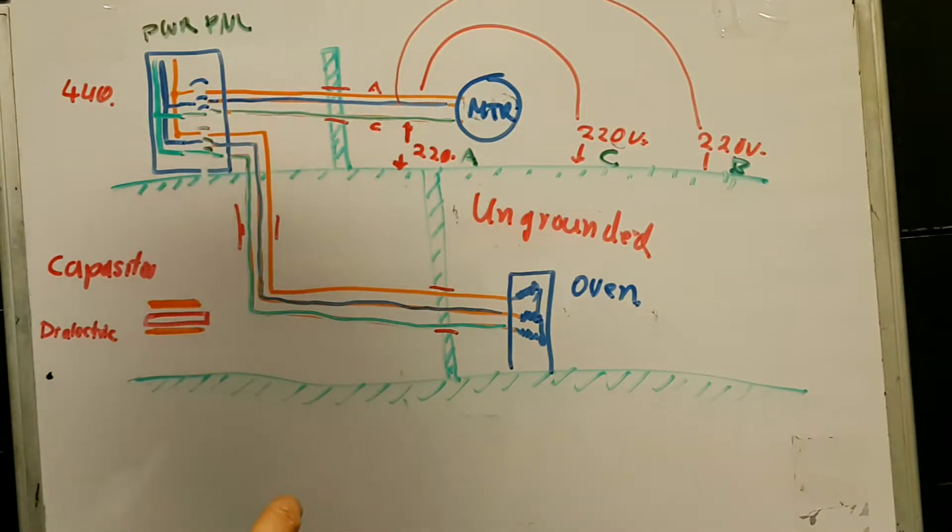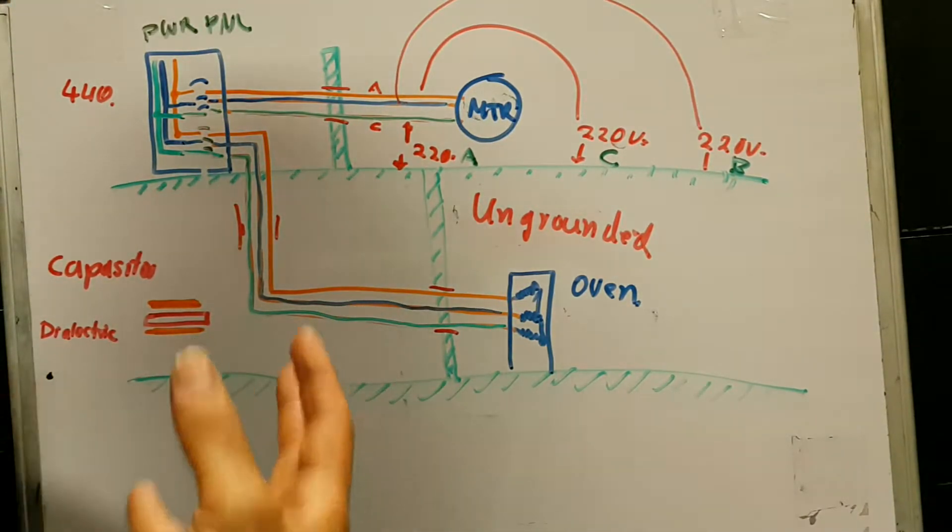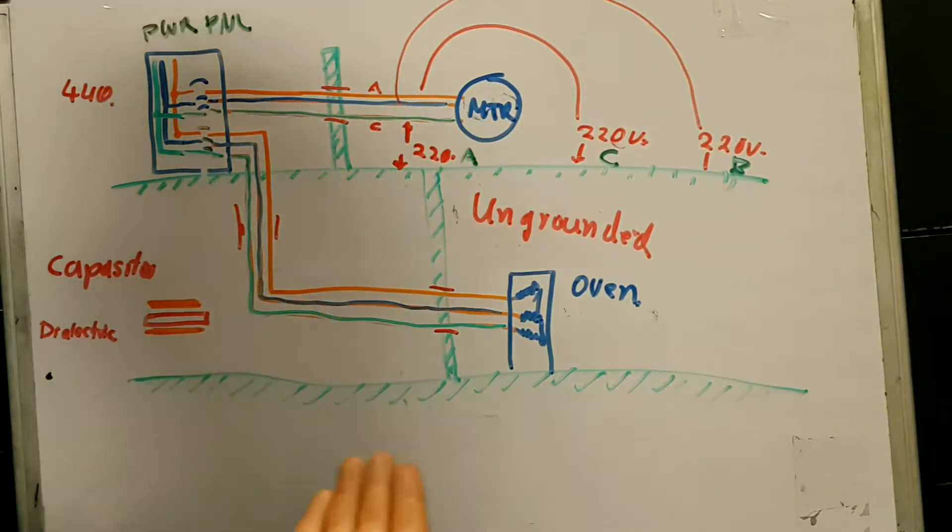That's what we got over here. The ship itself is a plate. The conductors inside, well, it's a plate, which is a very long conductor, and then the sheath, or the insulation of the conductor, functions as a dielectric. So there is a big capacitor, per se, between all of those phases and the ship.